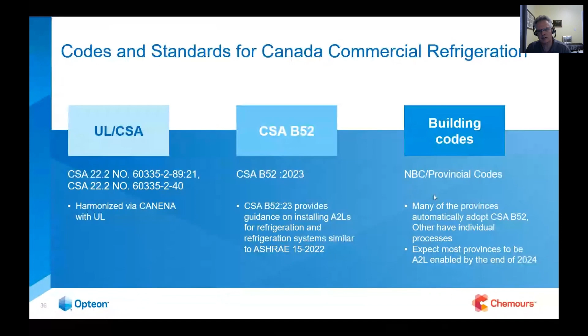Now, what does this mean for us in terms of installation? It's a little bit tricky for us to really get into detail on this, because this is up to the manufacturers of the equipment to some extent. But what we're going to see to minimize the chance of having a combustion event with A2Ls, we're going to see some things like refrigerant sensors. We're going to see ventilation air. We're going to see circulation air.